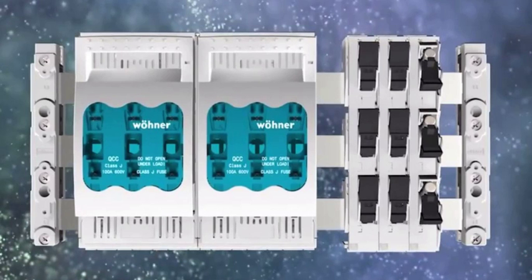Electrical busbar system, sometimes simply referred to as busbar system, is a modular approach to electrical wiring, wherein instead of standard cable wiring to every single electrical device, the electrical devices are mounted onto an adapter which is directly fitted to current-carrying busbar.